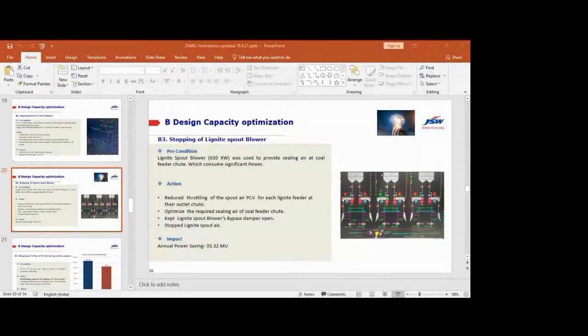Stopping of lignite spout blower. The lignite spout blower provides the sealing air at the coal feeder chute. It is a 630 kilowatt blower. Here we can see the lignite spout blower receives the intake air from the primary air fan, which is pressurized and sent as sealing air for the lignite feeder.